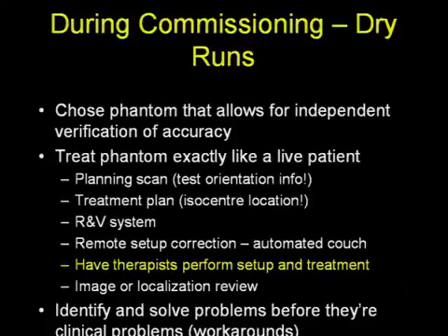However, the crux of commissioning, in my opinion, is to perform dry runs using the new technologies, and typically involving phantoms that allow for independent verification of accuracy. So one selects a phantom. It doesn't need to be anything fancy. A lead ball bearing on a cup of styrofoam can do quite nicely in a pinch, although it may lack some orientation information.